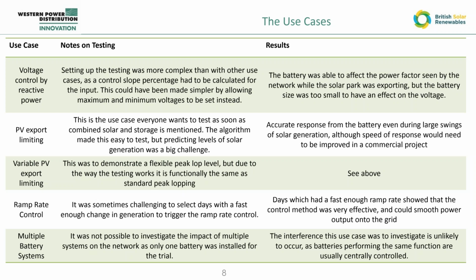Variable PV export limiting. This is to demonstrate that you don't have to just set the battery at a particular level, you can change it day by day. So if there were different network conditions, let's say something was being repaired or replaced, you could artificially lower the export limit for a time and still make use of some of your PV power. Realistically, within this testing, those were tested at the same time because every export limit that I placed was a variable one because I could set it manually.